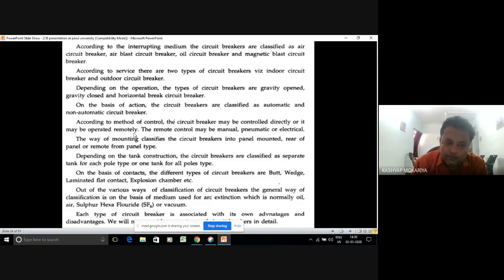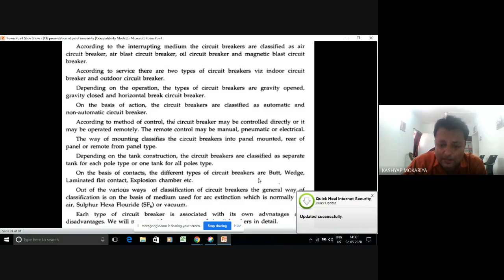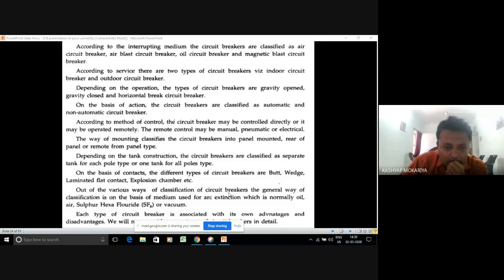The way of mounting classifies the circuit breaker into panel mounting, rear of the panel, or remote from the panel. On the basis of contacts, the different types of circuit breaker are butt type contact, wedge, laminated, flat contact, and explosion chamber type. These are the different types of contact which are used. Out of the various ways of classification of circuit breakers, the general way of classification is on the basis of the medium used for arc extinguishing: oil circuit breaker, SF6 circuit breaker. So these are the different types of classification.